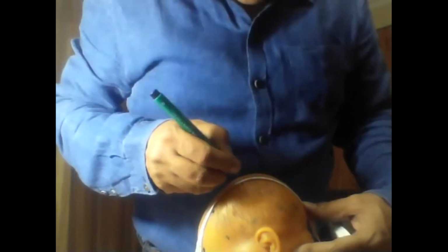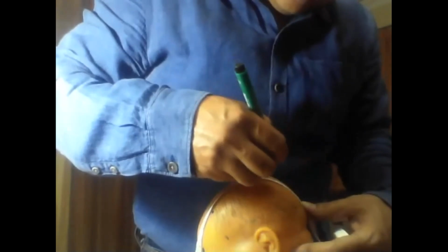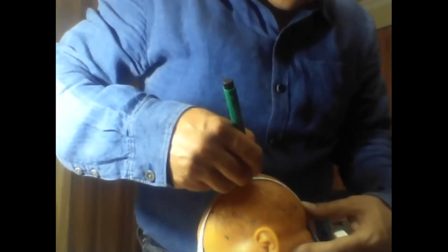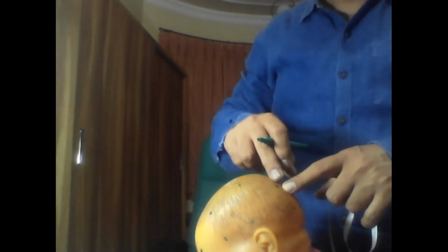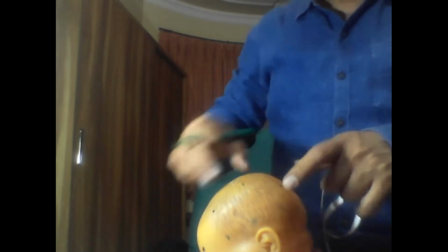This point is your F3. And from this 9 to this 18, the middle is 4.5. This point is actually your P3. However, in a sleep montage we are not interested in this, but in the EEG extended montage, this will come into the picture. So we have found P3 and F3.